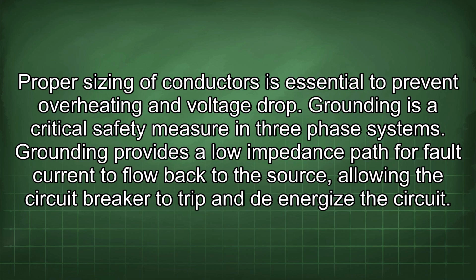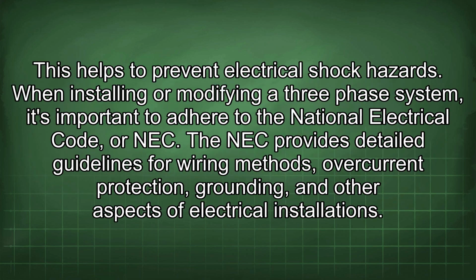Grounding is a critical safety measure in three-phase systems. Grounding provides a low impedance path for fault current to flow back to the source, allowing the circuit breaker to trip and de-energize the circuit. This helps to prevent electrical shock hazards.